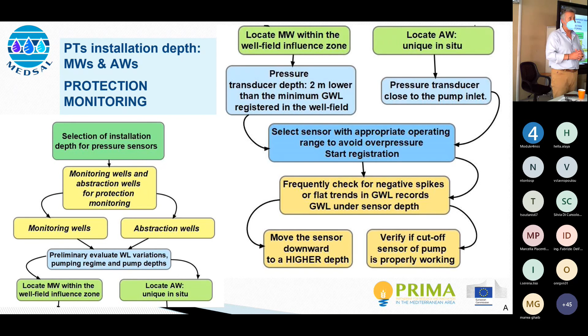However, in practical terms, if you are installing your sensor in the abstraction well, and you don't have a piezometric tube in the abstraction well, there is no way you can install your pressure transducer underneath the pump inlet. It's dangerous, and you don't have the angle. So, as a practical rule of thumb, if you manage to install your pressure transducer at a depth pretty close to the pump inlet, not above it, you are bound to be okay and safe in terms of making the appropriate measurements. Let's see this next one, please.